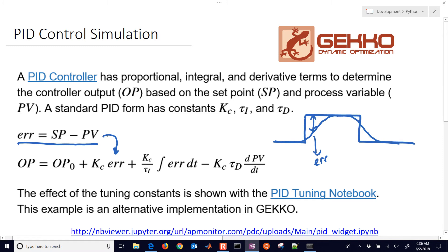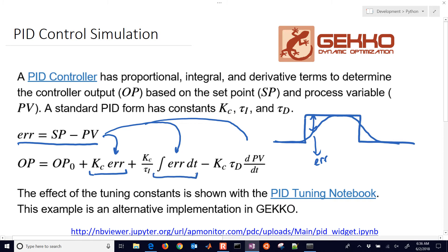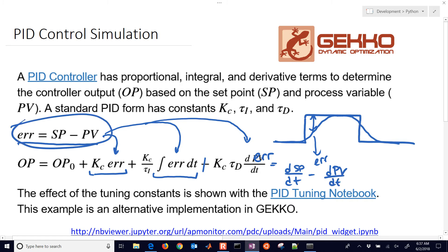That error comes in at different places. The first is the proportional term, the second is the integral term, and the third is the derivative term. Normally you'd have error in the derivative, but we break that apart into set point and process variable pieces. To avoid derivative kick, we just get rid of the set point changes and go with negative PV instead.